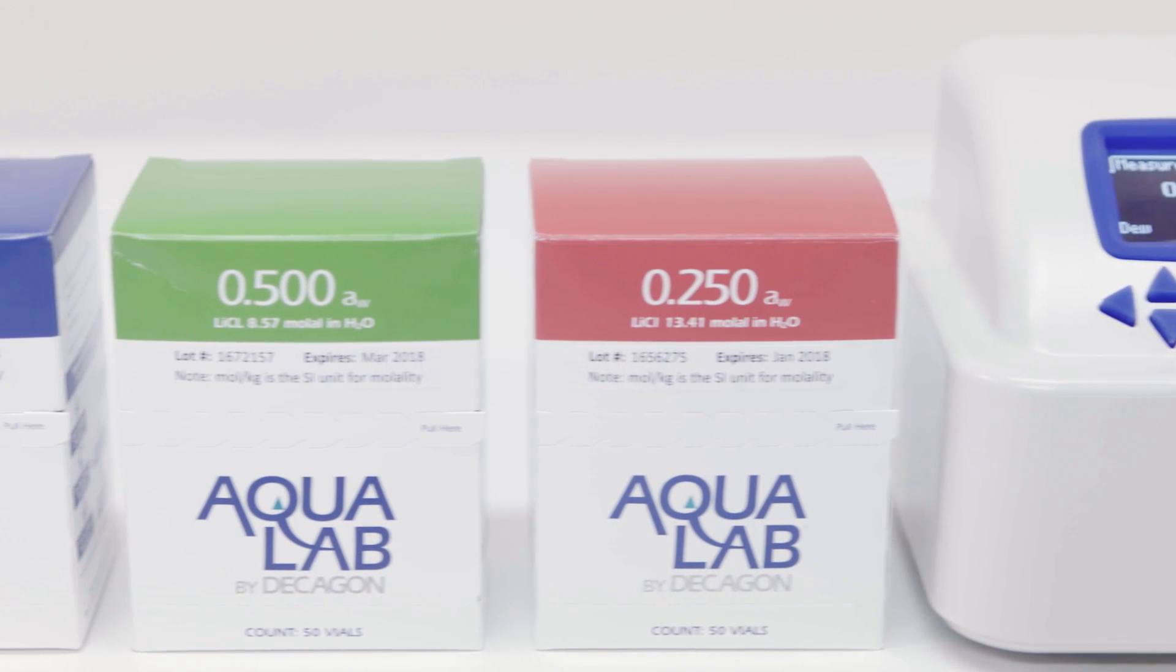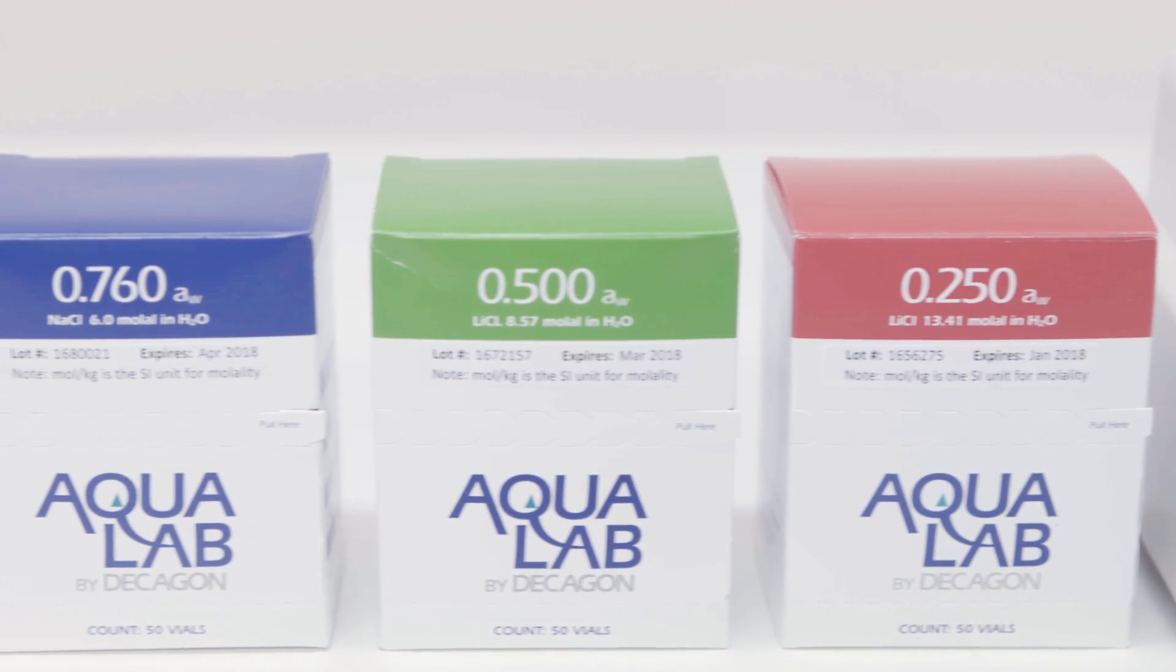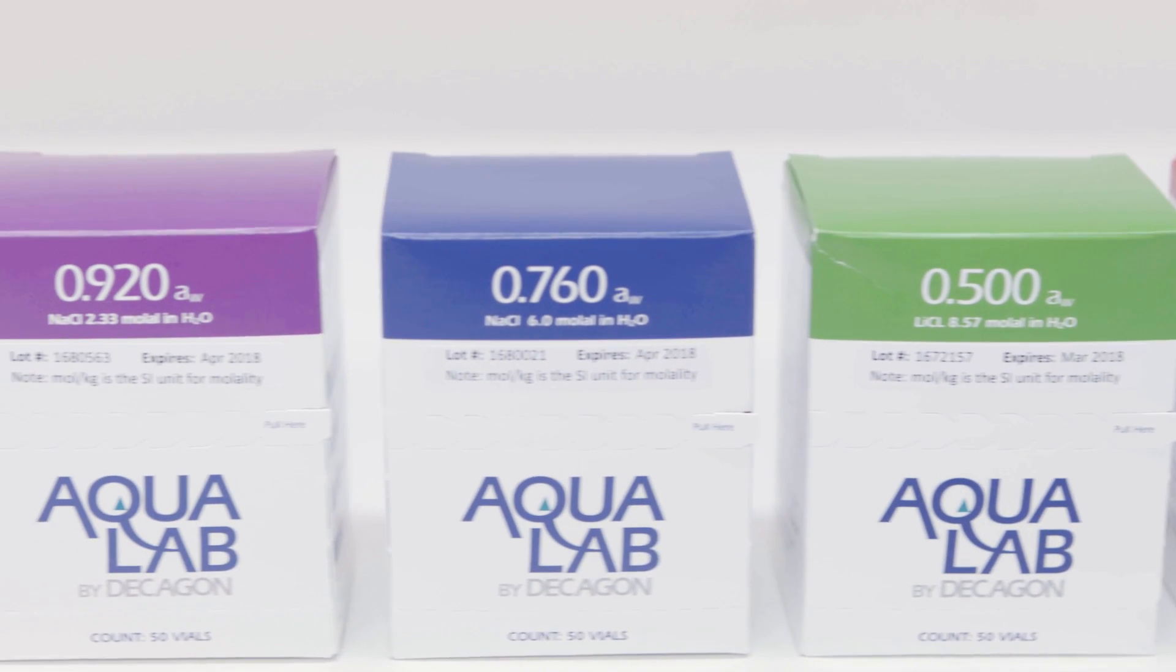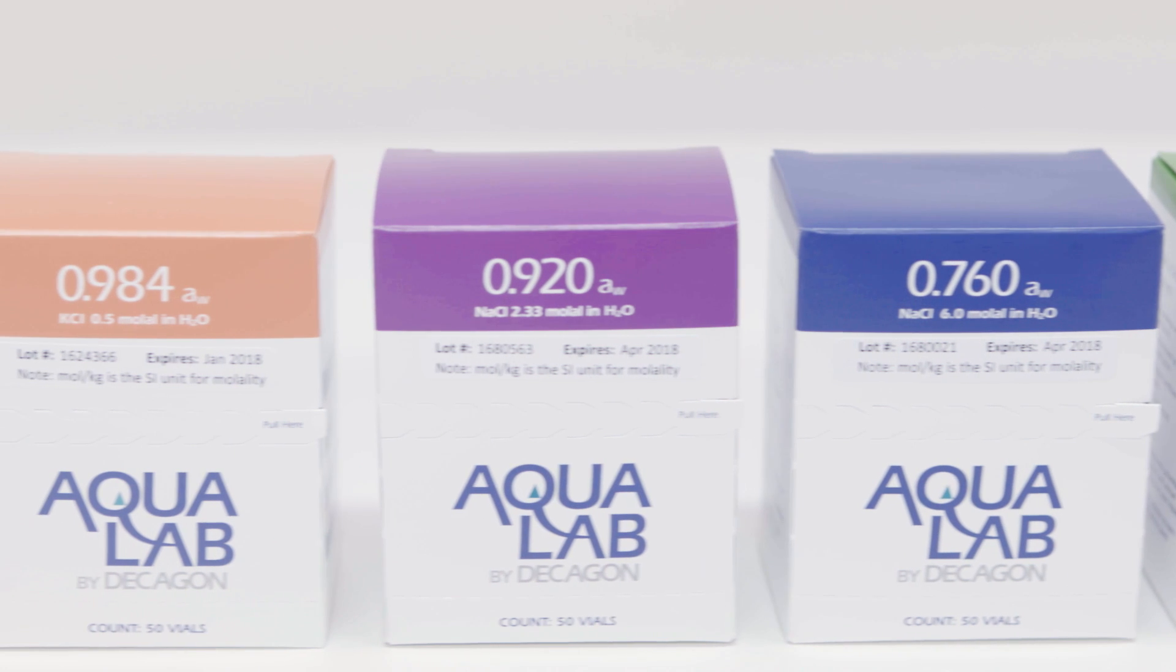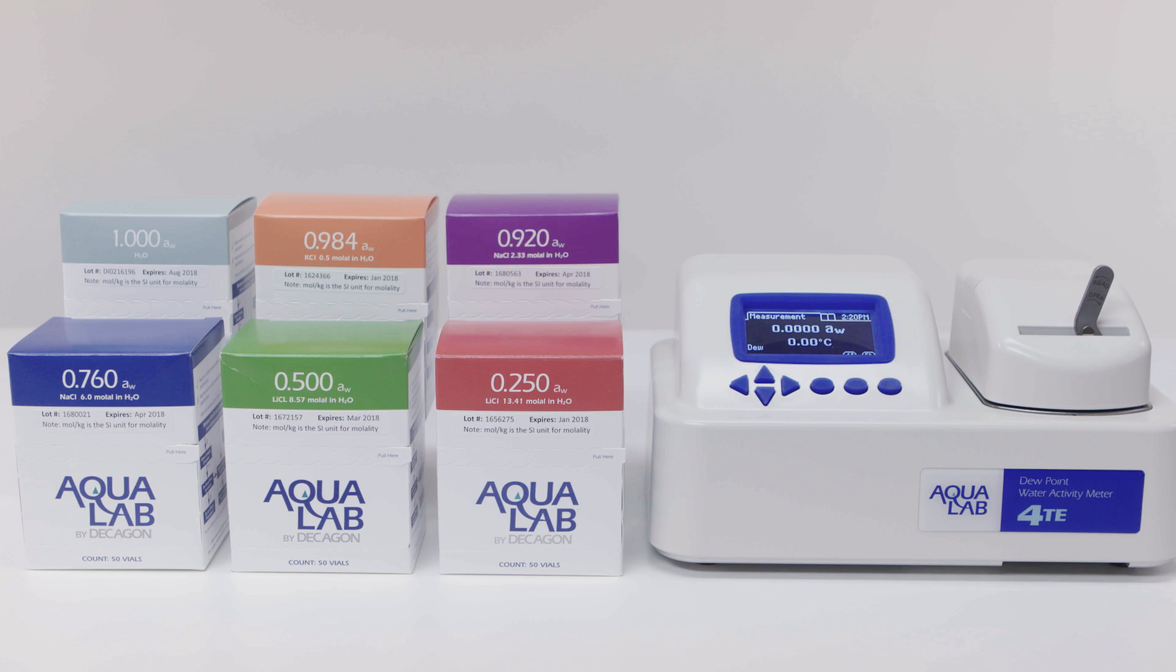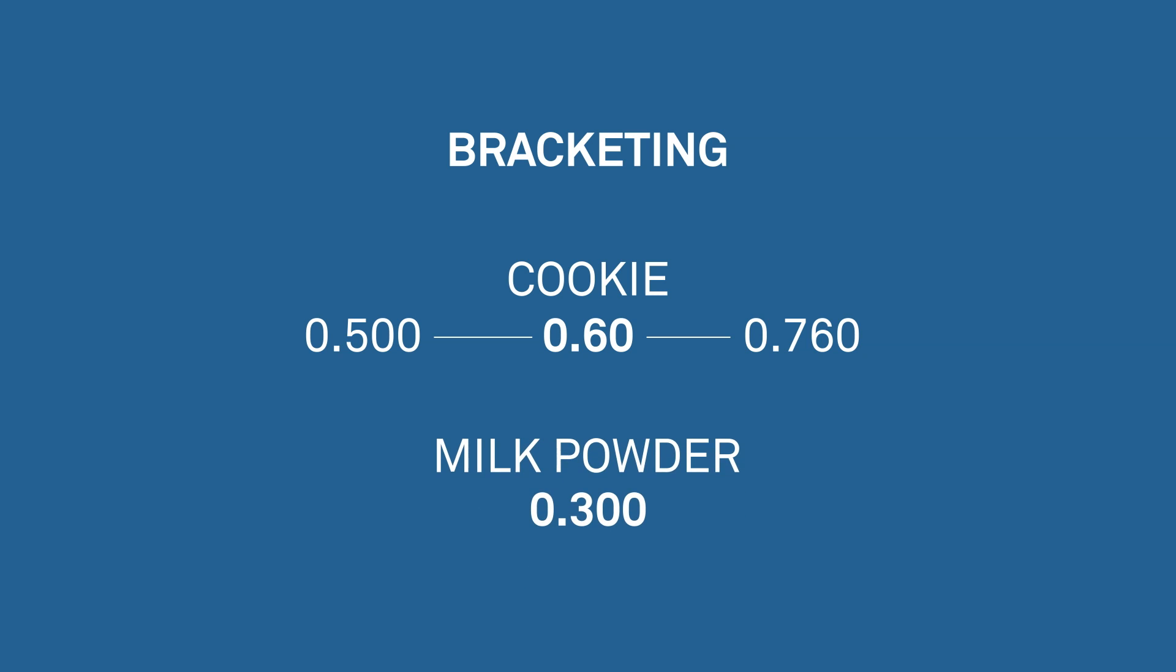There are five verification standards available for your instrument: 0.250, 0.500, 0.760, 0.920, and 0.984. These salt solutions are tested with a densiometer which allows us to know their concentration very accurately. The best way to verify your instrument is to use a technique we call bracketing. If you are measuring a cookie that typically has a water activity of 0.60, you should use the 0.500 and 0.760 standards to verify. If you are measuring milk powder in the 0.3 range, you should use the 0.250 and 0.500 standards to verify.